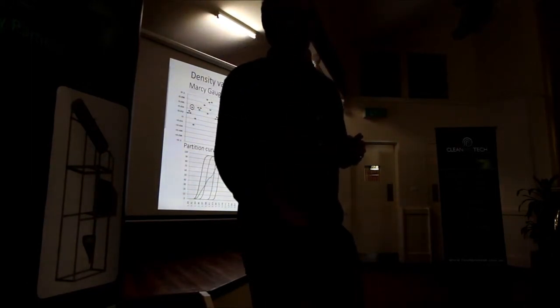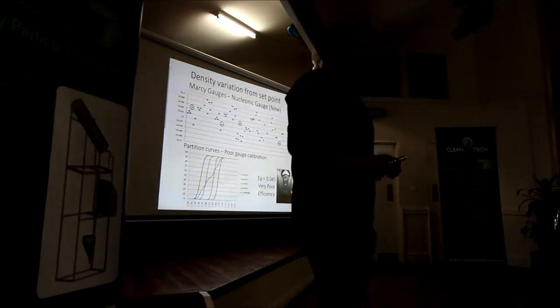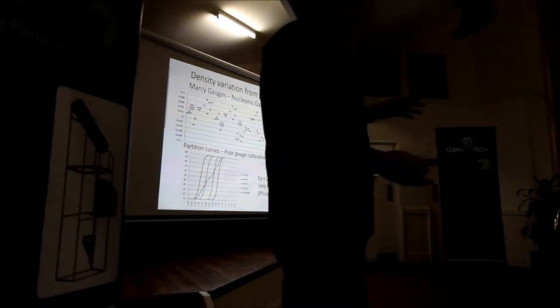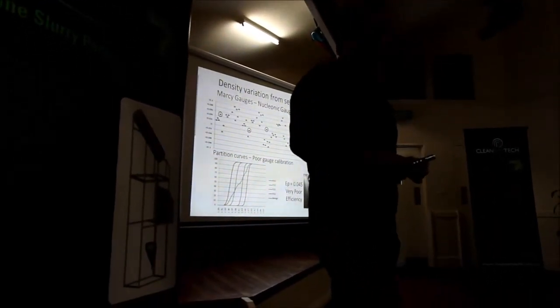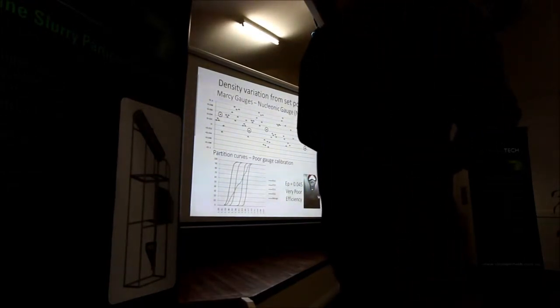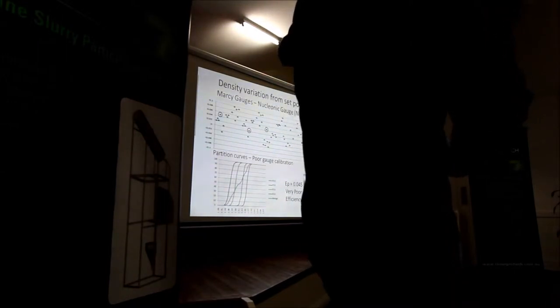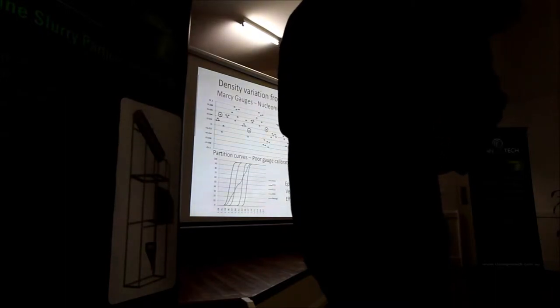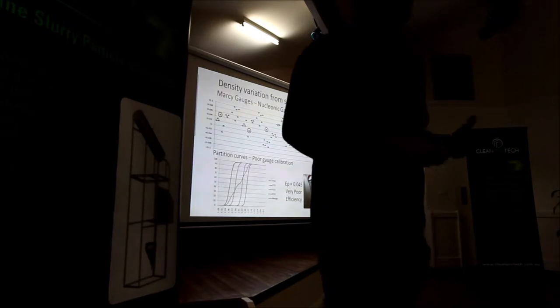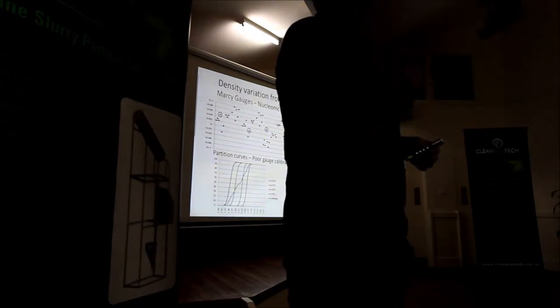Our measurement method at the time was a Marcy gauge on a hanging scale. I went out over about six to eight weeks and just spent hours under the tapping points taking Marcy gauges. That graph at the top shows the variability of our results. At its worst, this is variability from the set point the gauge is telling us — it was right up at like 0.1, which is terrible. That's worse than those previous graphs. I've taken four of those points, drawn the partition curves presuming the same EP and H cyclone, and plotted the system efficiency — it's still rubbish. So we'd spent all this capital, but there's no point having the VSDs control under good pressure when we've got variation like this in the density gauges.